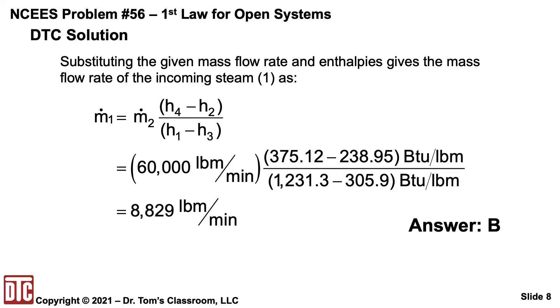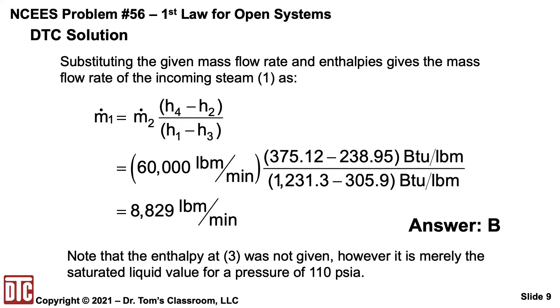Substituting all of these enthalpies into the expression, we have 60,000 pounds per minute for M2-dot, and then the difference in enthalpies H4 minus H2 divided by the difference H1 minus H3 gives about 8,829 pounds per minute, which is answer B. Note that the enthalpy at state 3 was not given; however, it's merely the saturated liquid value for a pressure of 110 psi.